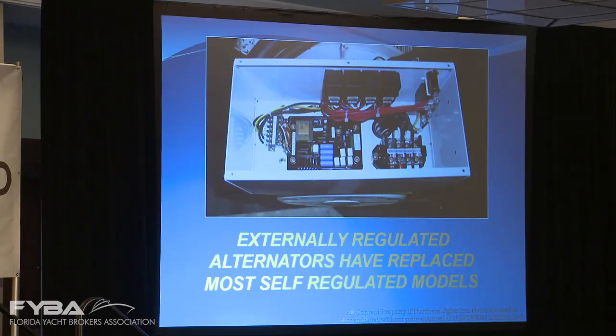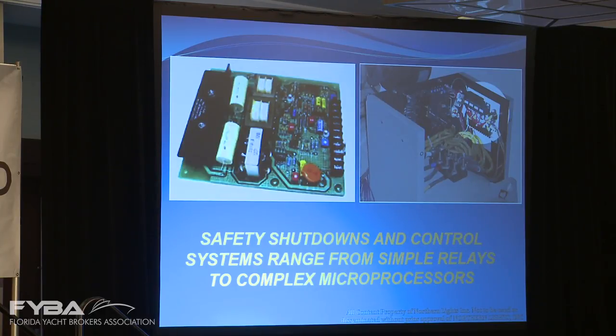So earlier generators didn't use AVRs, later ones do, and we have very few self-regulating models on the market anymore. One critical thing about generators is how we start and stop them automatically and how you protect yourself from an expensive failure. And to do that, you have some sort of a safety shutdown and control system. So the safety shutdowns and control systems vary quite a bit.